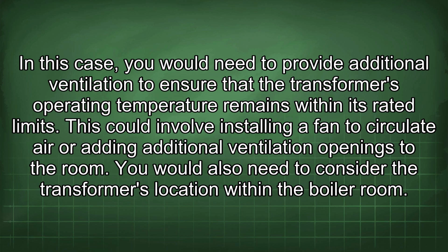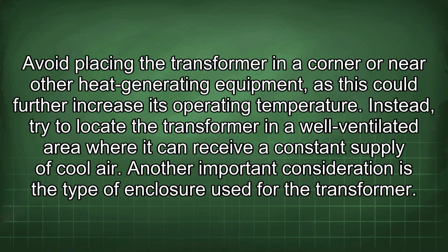You would also need to consider the transformer's location within the boiler room. Avoid placing the transformer in a corner or near other heat-generating equipment, as this could further increase its operating temperature. Instead, try to locate the transformer in a well-ventilated area where it can receive a constant supply of cool air.